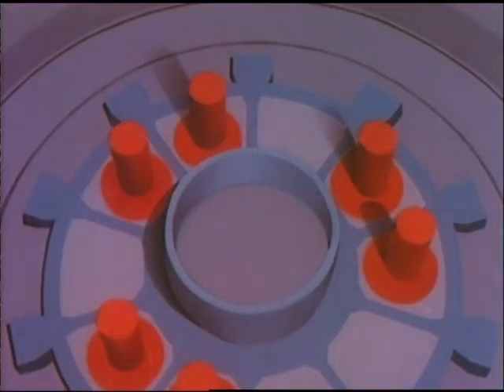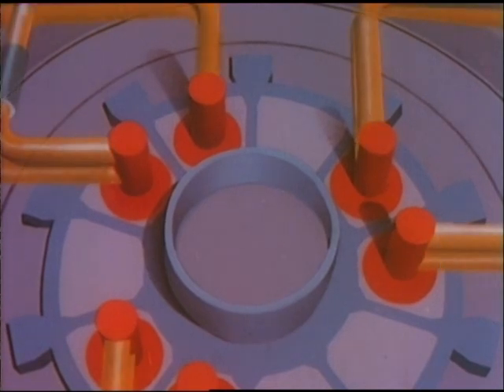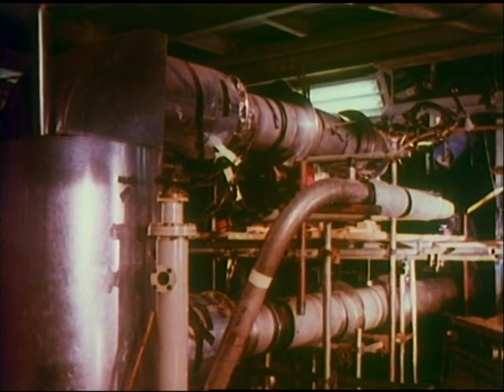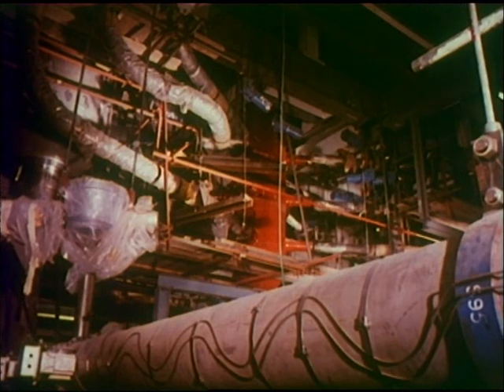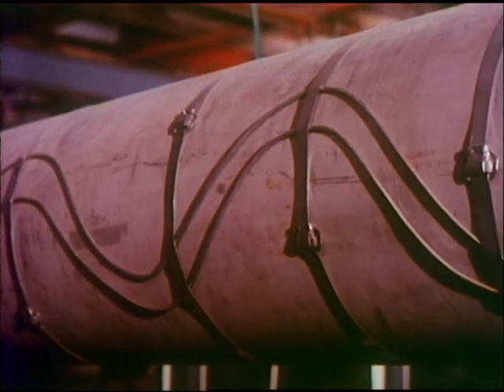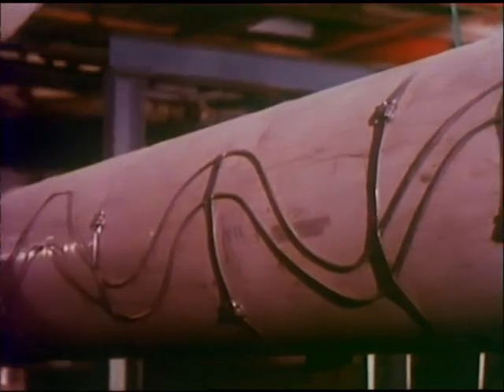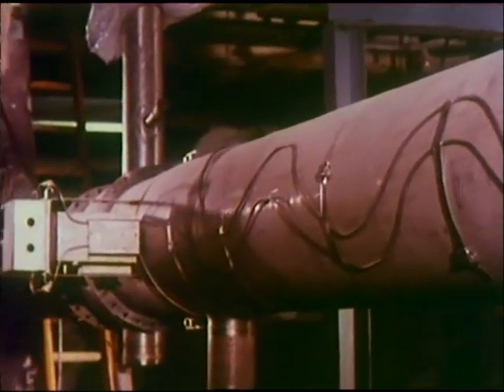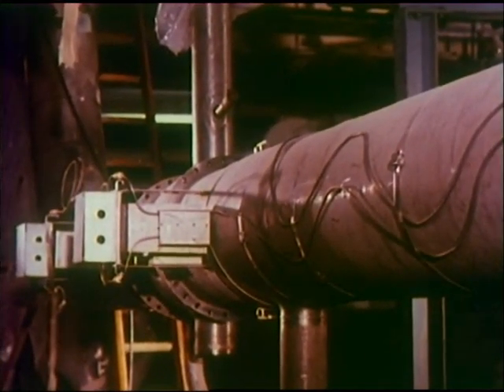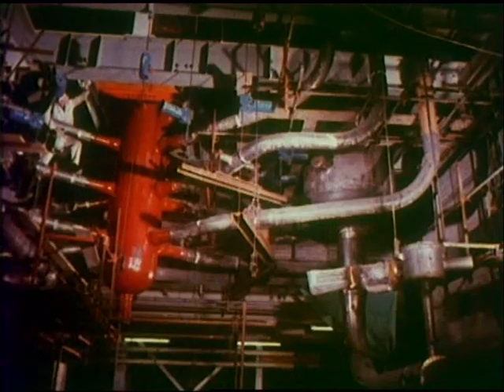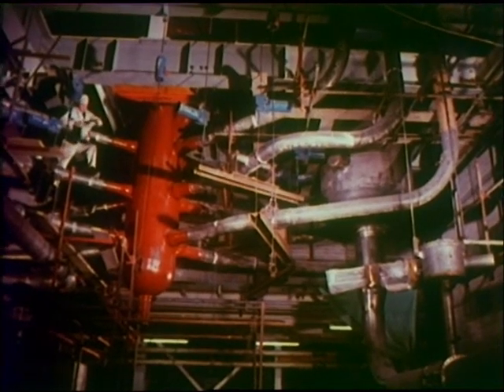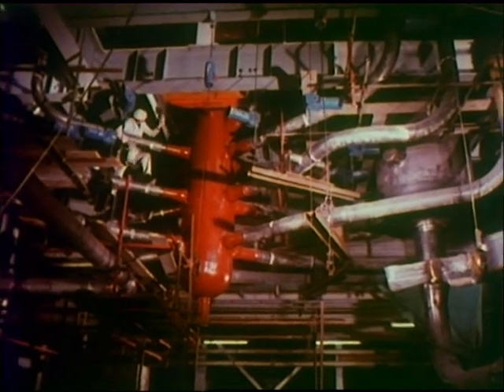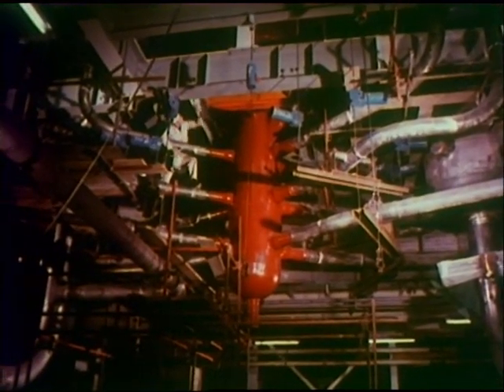The roof was designed with 6 penetrations for the intermediate heat exchangers, which transfer heat into the secondary sodium circuit. These 6 heat exchangers were next installed in the roof. Before lagging was applied, trace heating elements were attached to the secondary sodium piping. These would come into operation during periods of shutdown. The sodium freezes at 98 degrees centigrade. The steam generating plant incorporated 3 secondary sodium circuits, any one of which could be shut off independently without closing down the reactor.